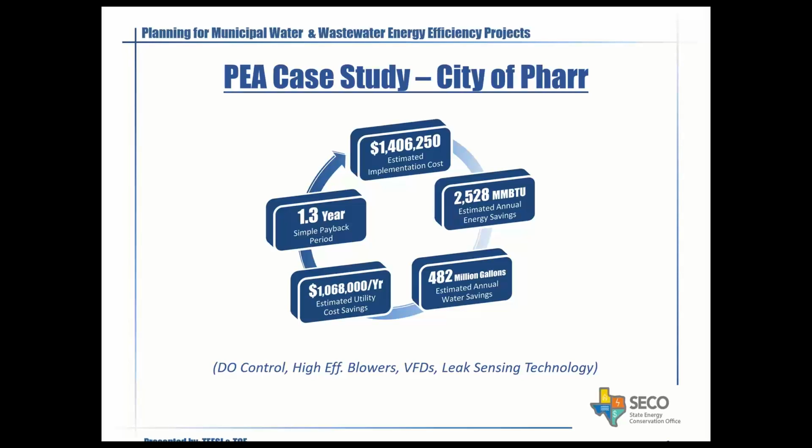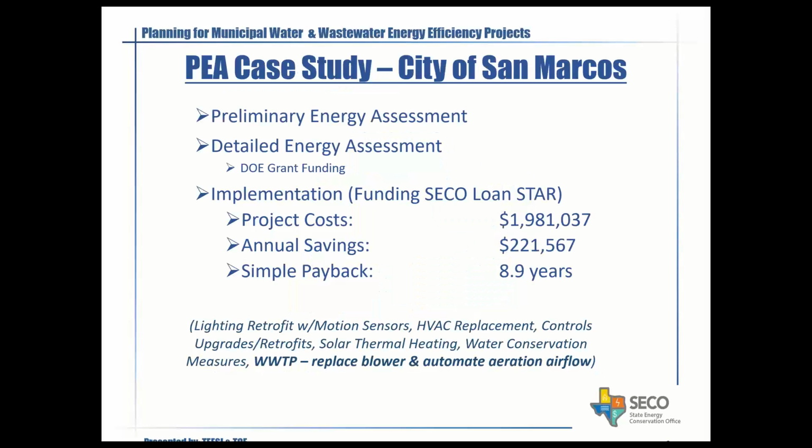And now these systems that are gaining this leak sensing technology are getting well under the 5% level and hitting the 2% level or less. So particularly if you're a city that has an unaccounted for water rate in the 20 percentile, this leak sensing technology will really save a lot of money quickly. The other thing is that you can also see a leak if there's a puddle of water, so that's another way to look at these things. But anyway, technology is advancing and it is available, and it could be utilized.